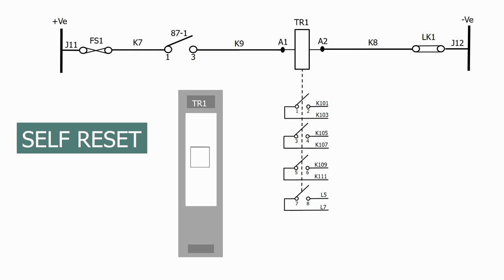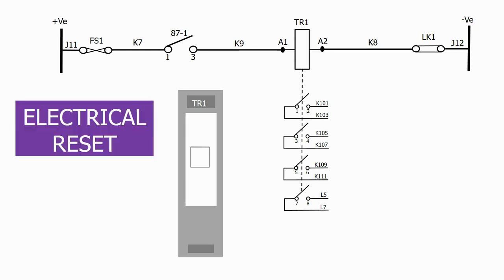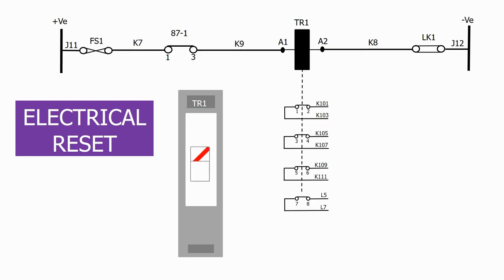The next option is electrical reset. In this configuration, when the relay coil is energized, the flag operates. But this time, the flag and the contacts don't automatically reset when the initiation is removed and the coil de-energizes.